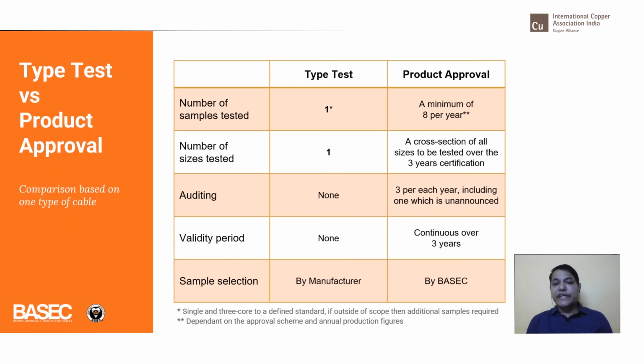And there is no auditing to check if there are any material changes done after 1 or 2 years by the manufacturers. When it comes to product approval, there are 3 audits done per year to see the process is the same, the materials are the same, nothing has changed. In fact, there is no validity period for type tests, which is now coming in by some utilities in the Middle East or Europe, and they are insisting that every 5 years, even if the material is the same, it has to be re-type tested.